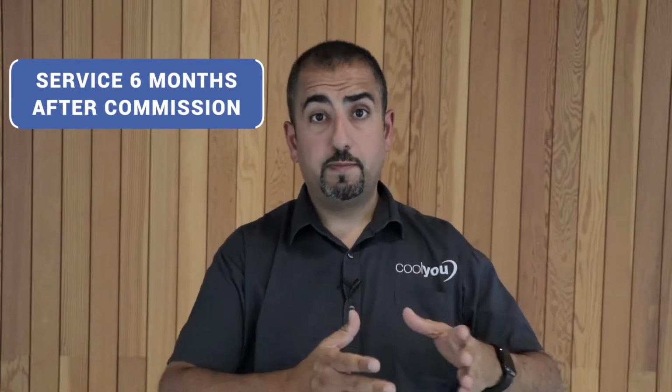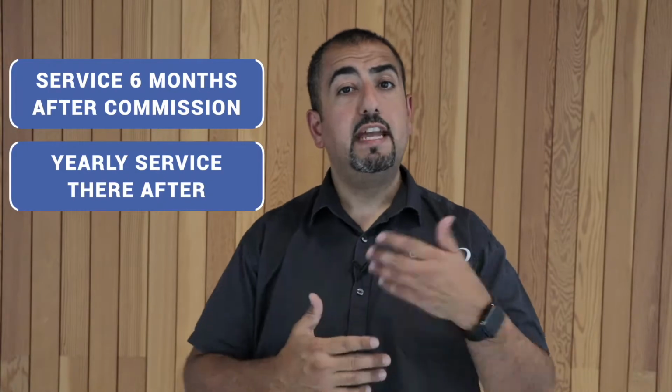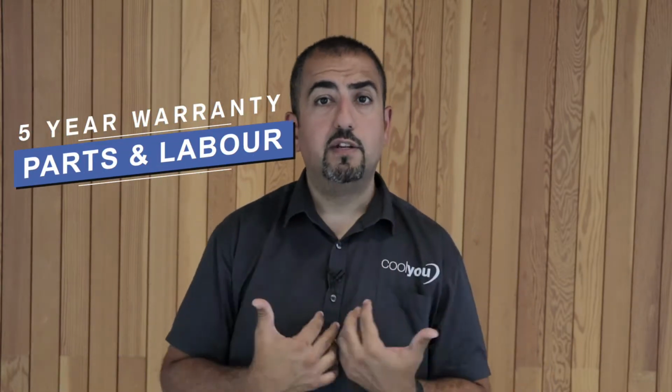It's a very common question, but quite simply, in the UK here, we follow the F-gas regulations. And as a registered company, we adhere to these rules, which simply means after your installation, your system needs to be serviced 6 months after it's been commissioned, and that's regardless of use, and then yearly thereafter. And by adhering to this, you then tick all the boxes, and it means you get your 5-year parts and labour warranty, which comes as standard with our units, and you are compliant with the regulations.